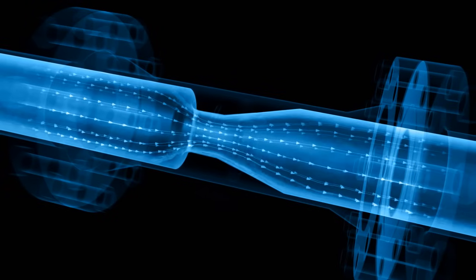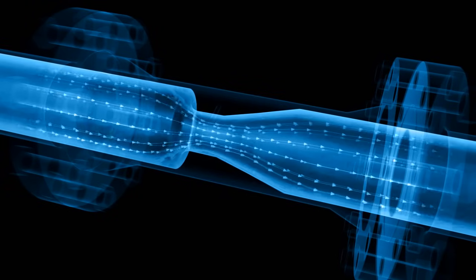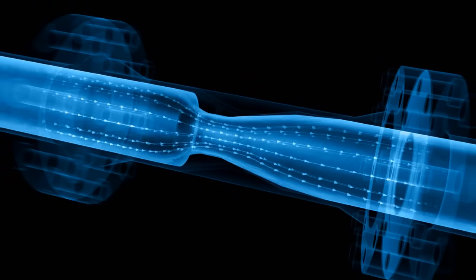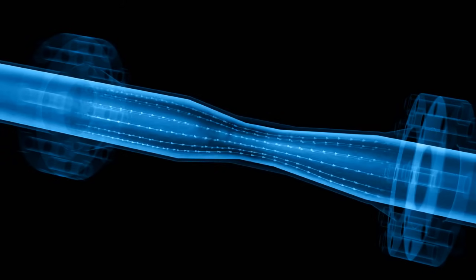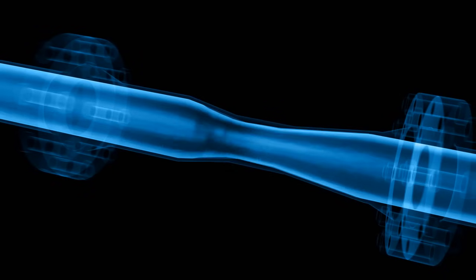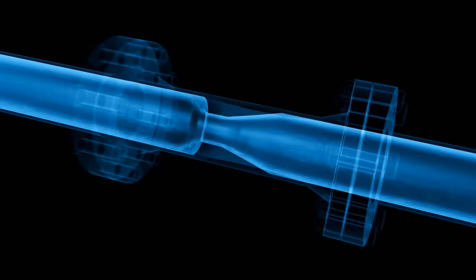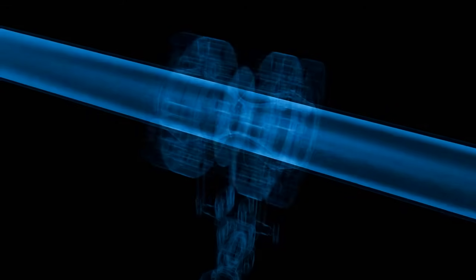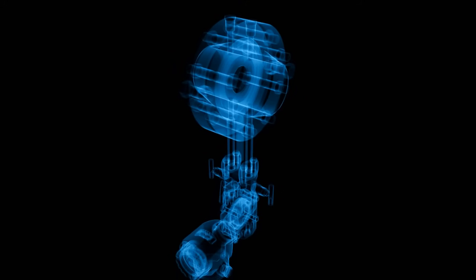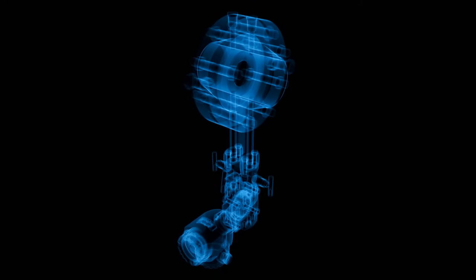Turbulence reduction is even greater with venturi nozzles and finally with venturi tubes, where the restriction is created by longer conical constrictions in the pipe wall. All these designs can be supplied with different restriction diameter sizes, so that the pressure loss and the differential pressure generated can be optimized for the process conditions.